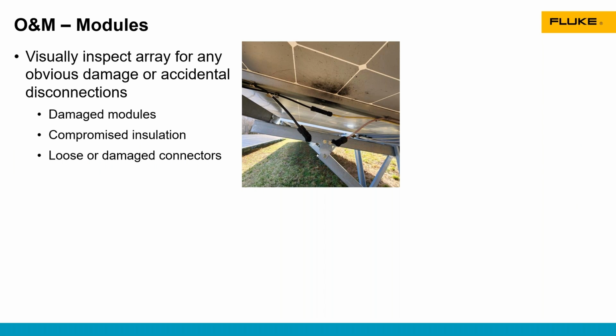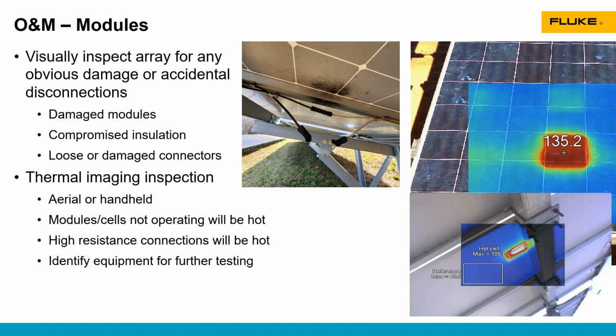Now, our modules are going to need maintenance as well. Visual inspection is the best place to start with our modules. So walking around the array, looking for any kind of damage, burnt out connectors like we see in the picture here, any shattered glass, damaged cells, things like that. We can also do thermal imaging of our modules. Aerial thermography is most common, but we can also use handheld thermal cameras to do spot checks of our modules.